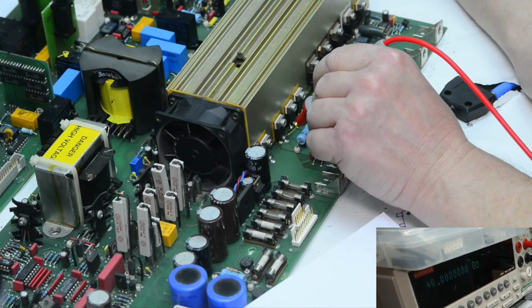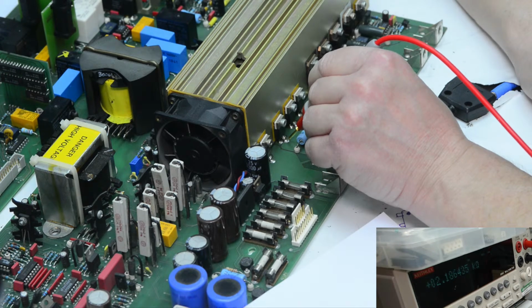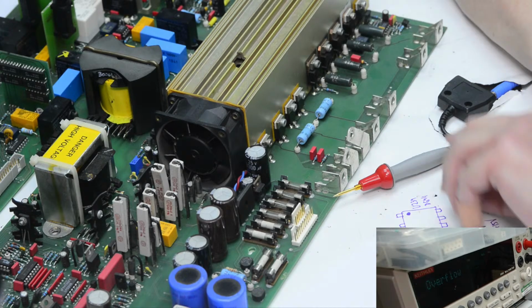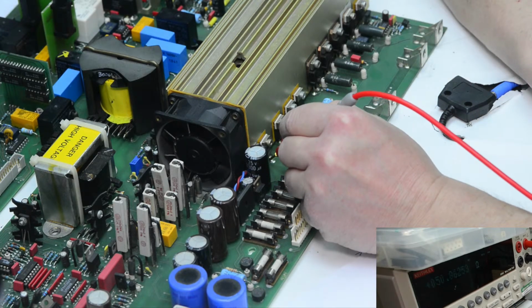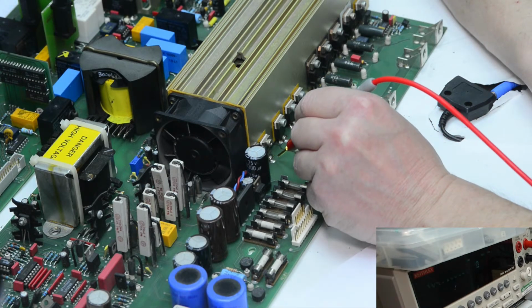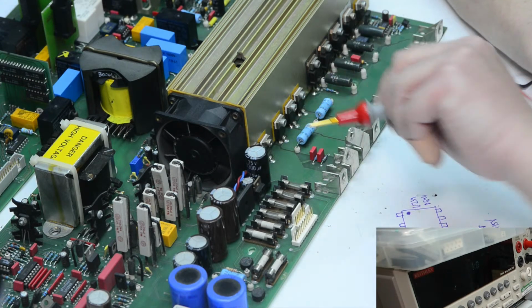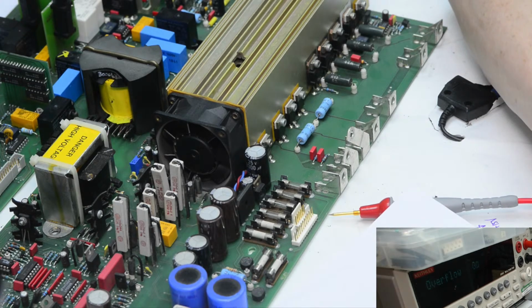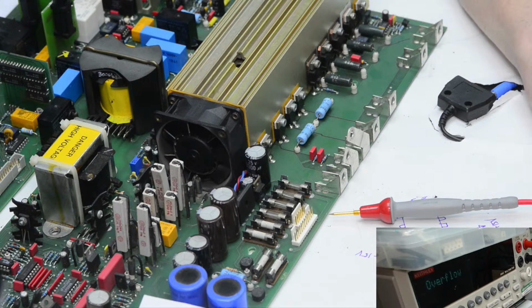Noise. What kind of noise are you seeing on the bridge? And also, what currents and resistances? Other than going higher than 1 kilo ohm, typically on 6010B I see the noise within 0.05 ppm or thereabout, but it also can depend on the conditions of the test, like parameter settings, how stable the resistor is, and all the different interference in the lab. So there are quite a lot of things that can go wrong when you're talking about sub ppm measurement.